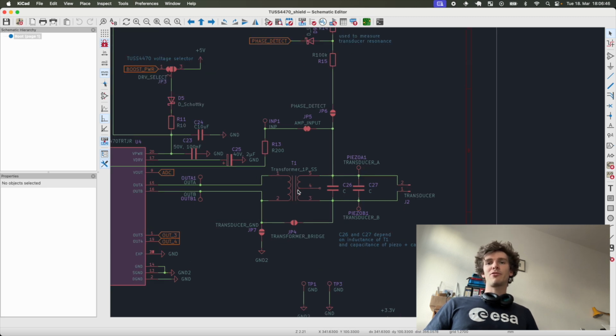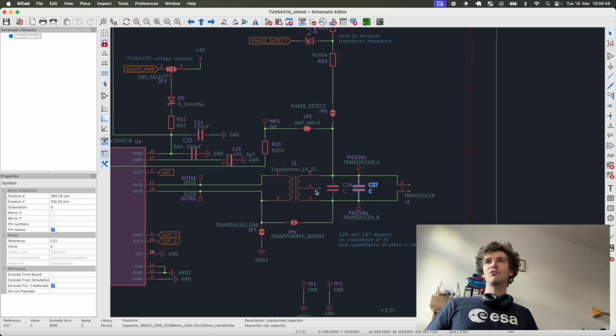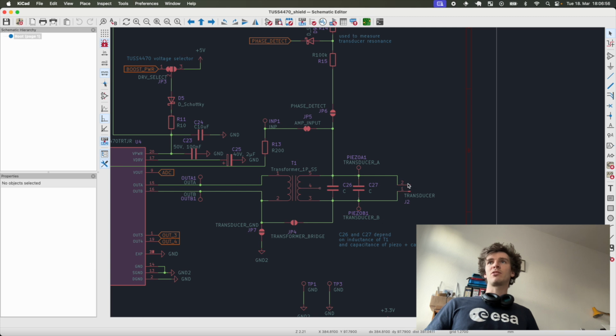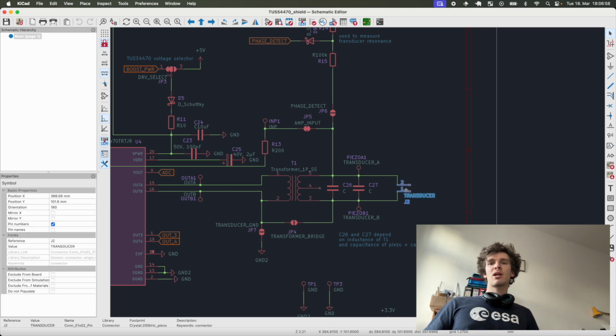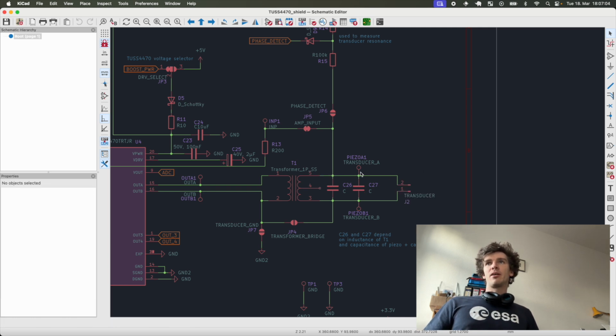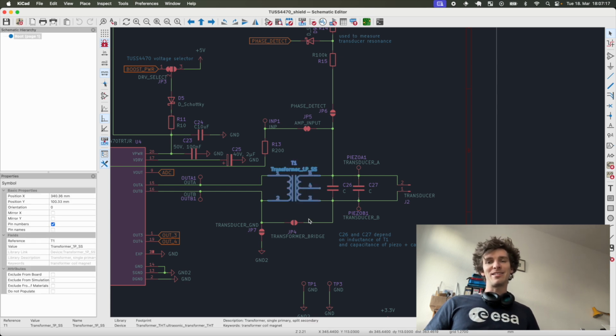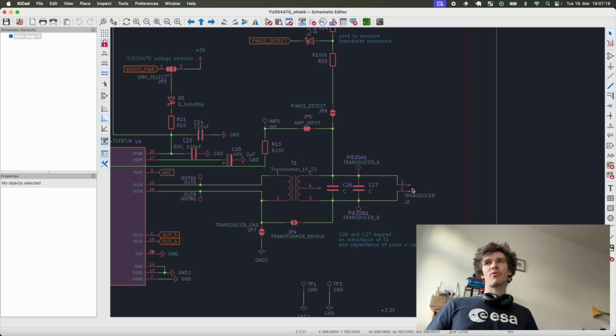The downside of using a transformer is that you have to match an LC circuit between the secondary coil, or the inductance of the secondary coil, with the capacitance of the rest of the circuit. That's basically the transducer, which has a capacitance around 200 to 800 picofarads, plus the cable, usually coax, which also has capacitance you need to consider. You have to match this using two matching capacitors to the inductance, forming an LC circuit tuned to the drive frequency, or the mechanical resonant frequency, of the transducer.